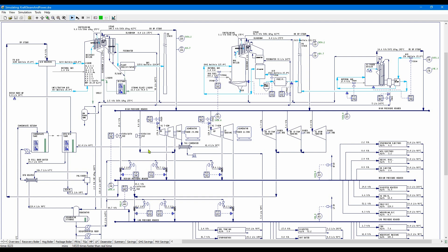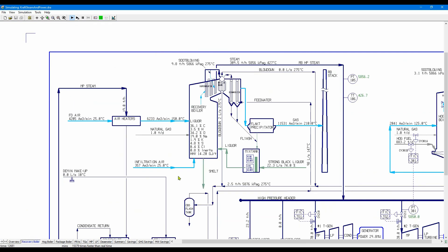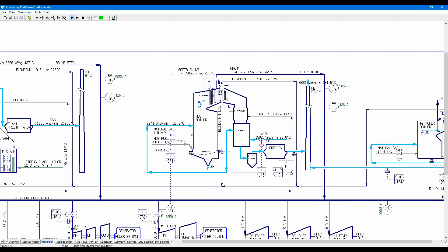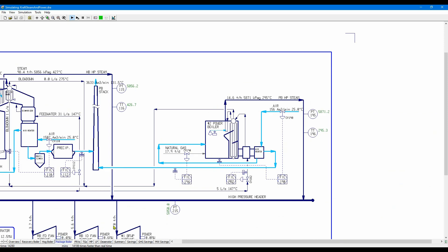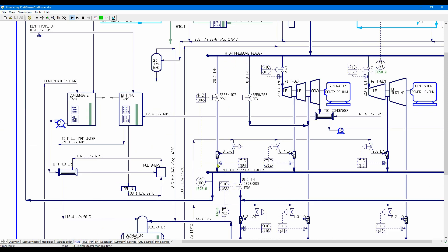Here we can see a power generation system that is typical. I'm going to take this for a drive starting from where data reconciliation left off a few minutes ago. What we have here is a recovery boiler that is burning black liquor, a hog boiler that is burning bark off the trees, and a package boiler. We have pressure reducing valves which can reduce the steam pressure but produce superheat which must be desuperheated and produces a bit more steam. On the other hand, we have turbo generators which can reduce the pressure and create electricity, reducing our electrical costs. The system is fairly complex — which are the best fuels, what ratio do we run the turbo generators, and how much steam do we put through the pressure reducing valves?